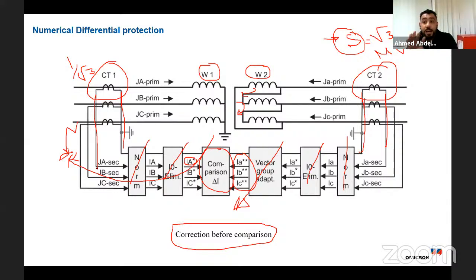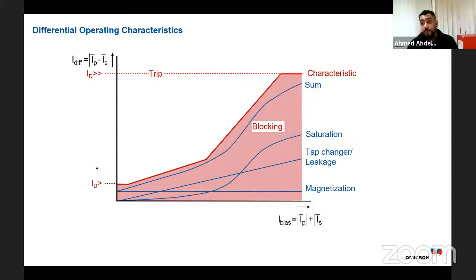This current, we call it the restraint current or the bias current. So there is a lot of terminology for the same parameter. We define the bias current, and you need to go back to your relay to understand exactly how the bias current will be calculated, because a Siemens relay is different from an ABB relay, different from Schneider, different from Schweitzer. Every manufacturer has its own bias differential equation, but all of them depend on Kirchhoff's current law.